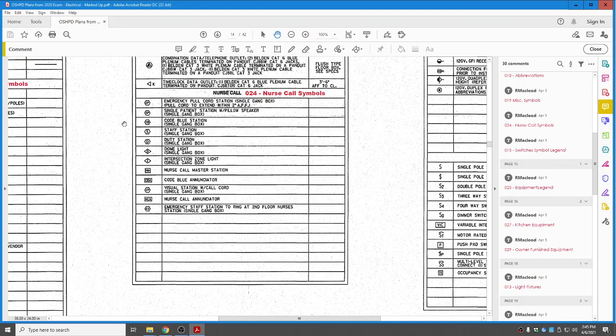Little all-in-one device there. Then you've got a CB, a code blue station that typically is placed inside all the patient rooms. In case a situation occurs, they can hit code blue and get staff there as quickly as possible. Then you have an S, a staff station, which is typically where the staff will be located, certain spaces. Then you've got a duty station that's similar to that. A dome light is typically a light that will be above a patient room door that when anybody hits a code blue button or the emergency pull cord in a patient room, the light over the door will notify any staff that's in the corridor, or they can just look down the corridor and see that light go on and respond immediately to that room. We've got intersection zone lights. We'll get to that another time.